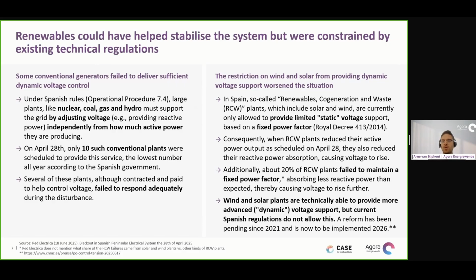Did the TSO provide enough resources or schedule enough resources? But not just this, the other factor that was key is that some of these plants, even though they were contracted and paid to deliver this voltage control service, they actually failed to respond adequately when the disturbance happened. So they actually didn't manage the problem, and some of them disconnected before we reached this 435 kilovolt level, and thereby made the problem worse.